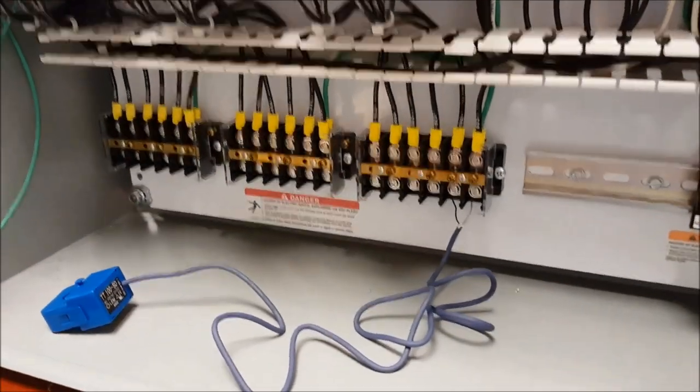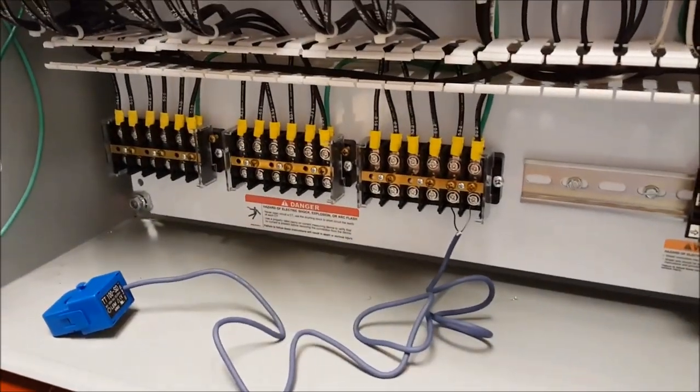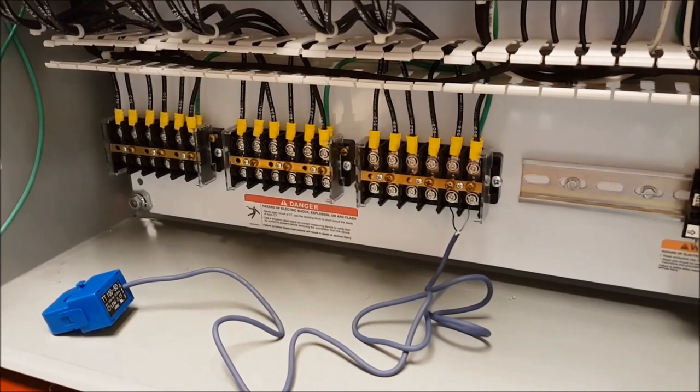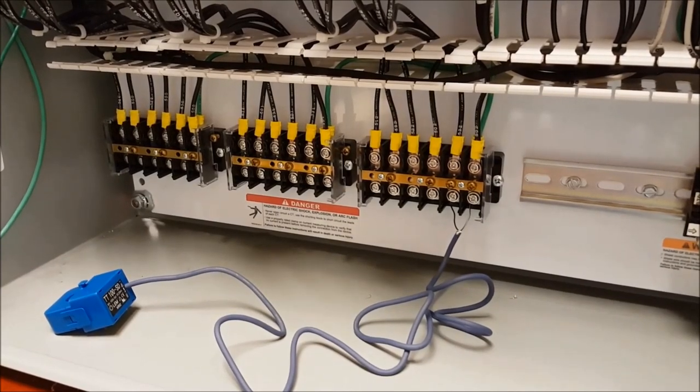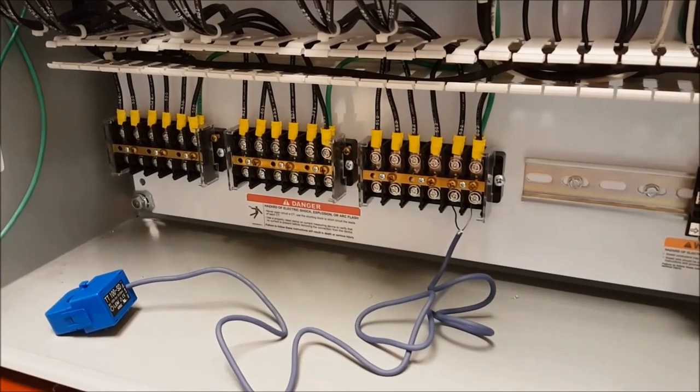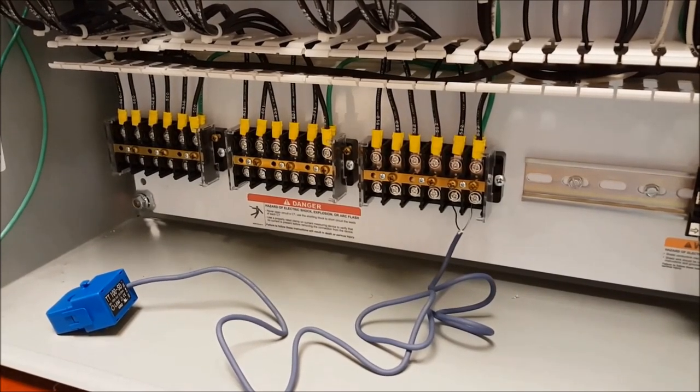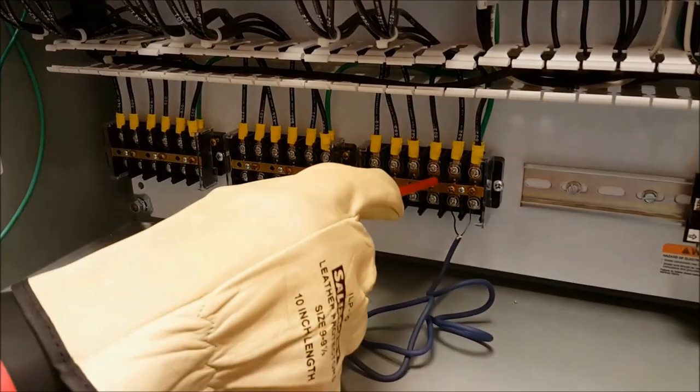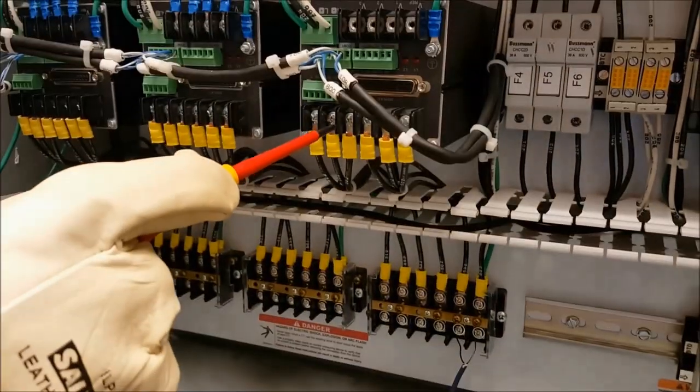Once the current transformer is properly shorted using the CT shorting block, it is safe to make wiring modifications on the meter side of the shorting block from here to here.